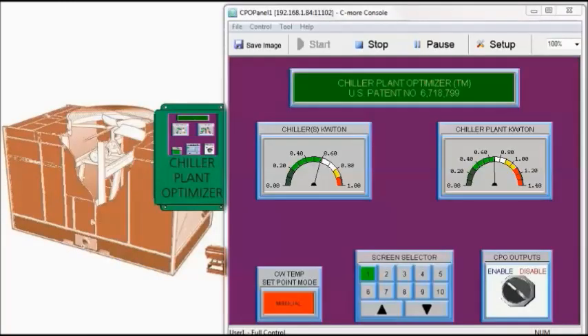So let's see variable flow condenser water in operation by viewing the display from a chiller plant optimizer. We have an outside wet bulb of 60 degrees Fahrenheit, and the load is 100%. Temperature set point here is in manual.